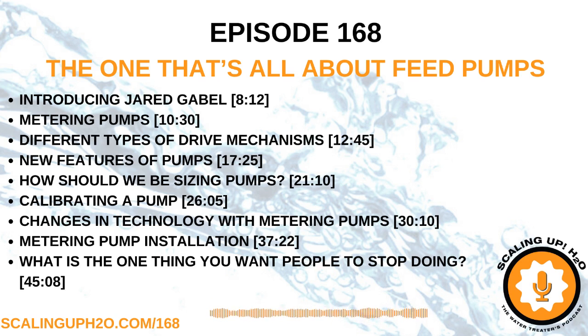Yeah, absolutely. Again, I'll point to the dosing head and the wet end of the pump. So this is where a lot of the troubleshooting comes. Sometimes it's that my pump isn't actually moving chemical. This could be due to some kind of air coming into the head, or it's not seating at the check balls. If this happens, there's some things that you can do. So you need to know how to take the dosing head apart. And those are usually in the IOM or maintenance instructions for a dosing pump. It's usually a pretty easy process.